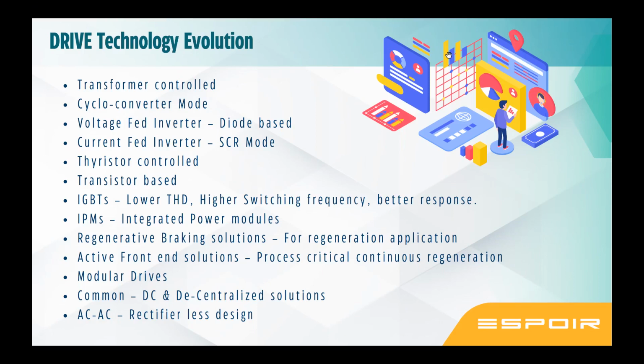There is a brand called Yaskawa who introduced the rectifierless design, which is called Matrix, a direct AC to AC drive. Now many other companies are adopting this. Finally, generally the industrial drives are 6 pulse, where there are some harmonic issues, and where the industry needs a very high-end power solution, they go for 12 pulse rectifiers in low voltage. In medium voltage, by default, it is 12 pulse, 18 pulse, 24 pulse.